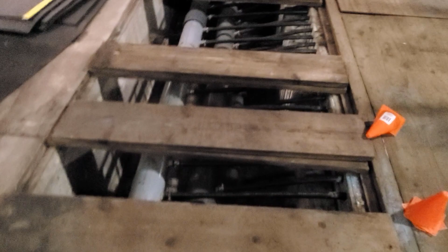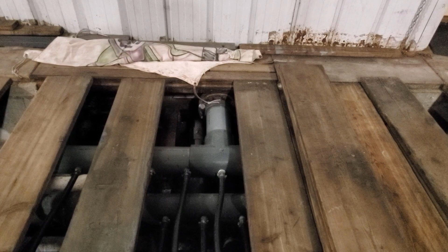So it probably would be good to bleed the ends of the header pipes. Anywhere there's a bleeder valve, we'll bleed a little air off just to make sure, but we're going to wait until it has time to circulate. Since we didn't really drain it down to the header, I don't think there's a lot of air in there, but some air probably got in because the chiller was empty.